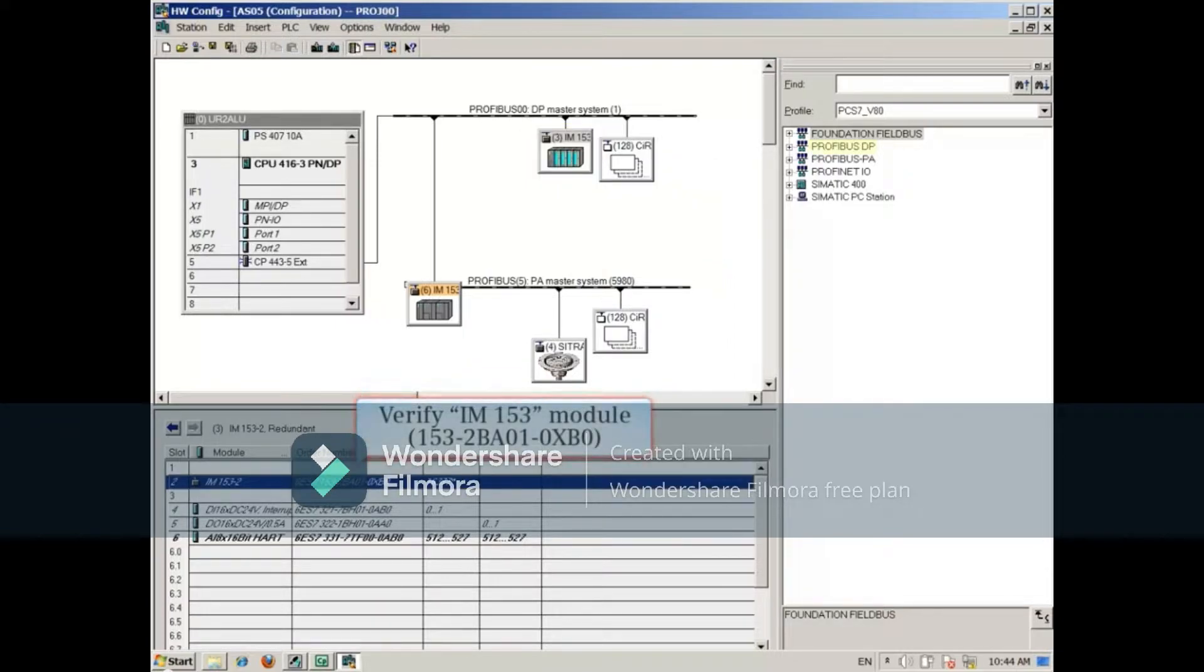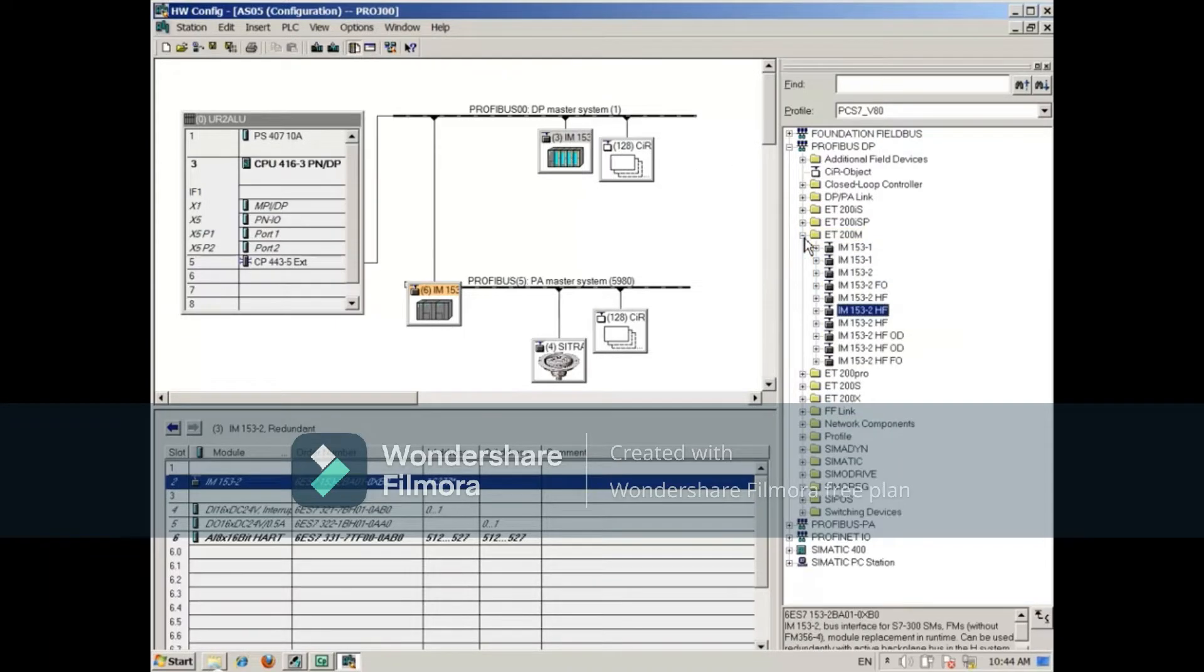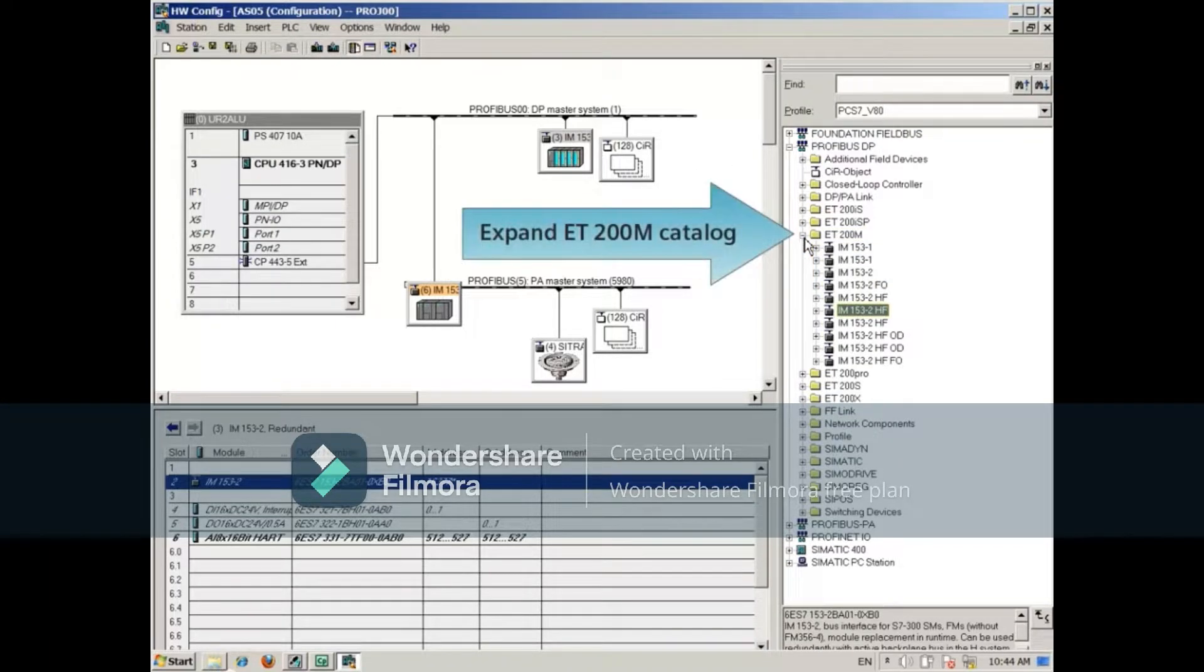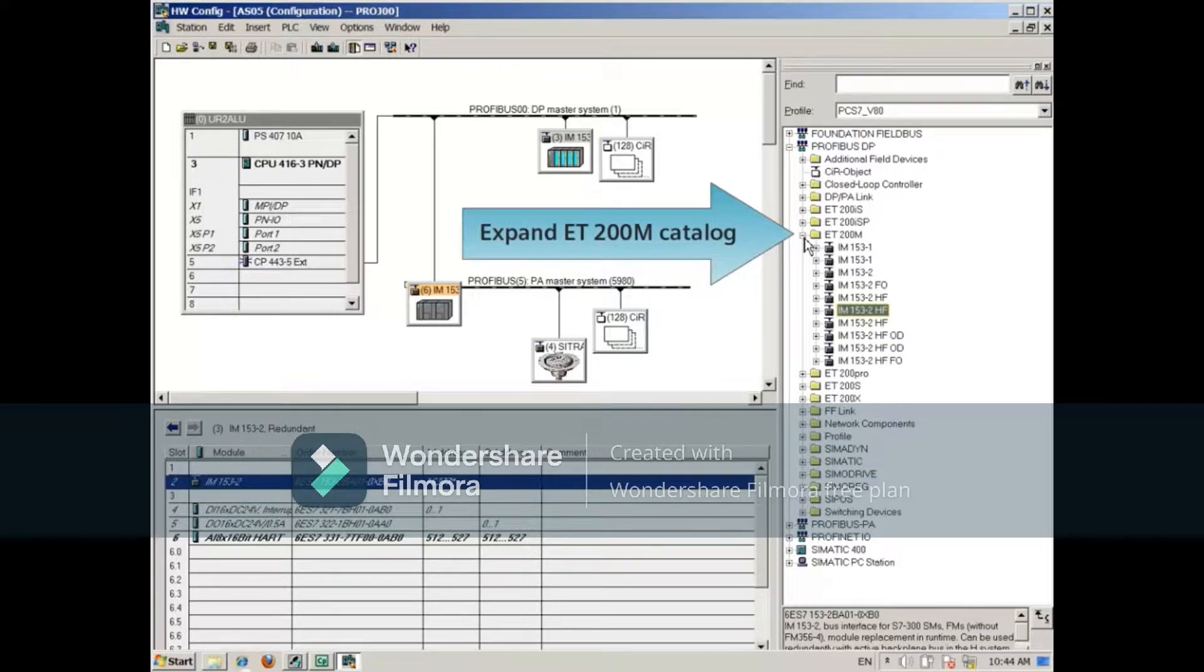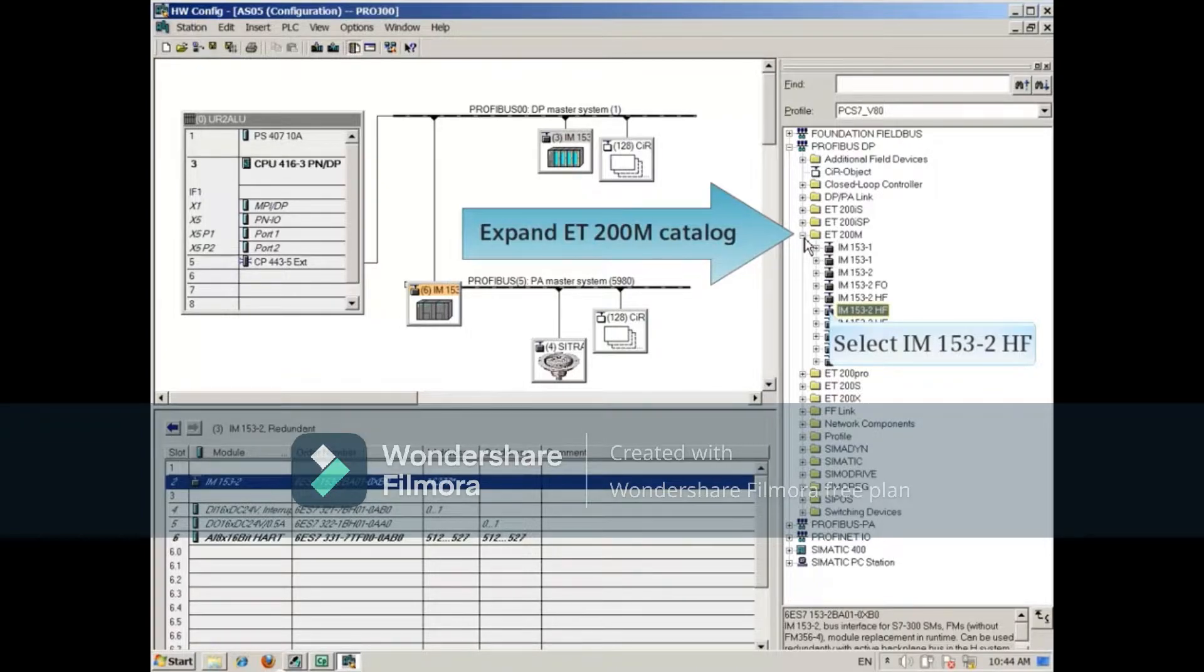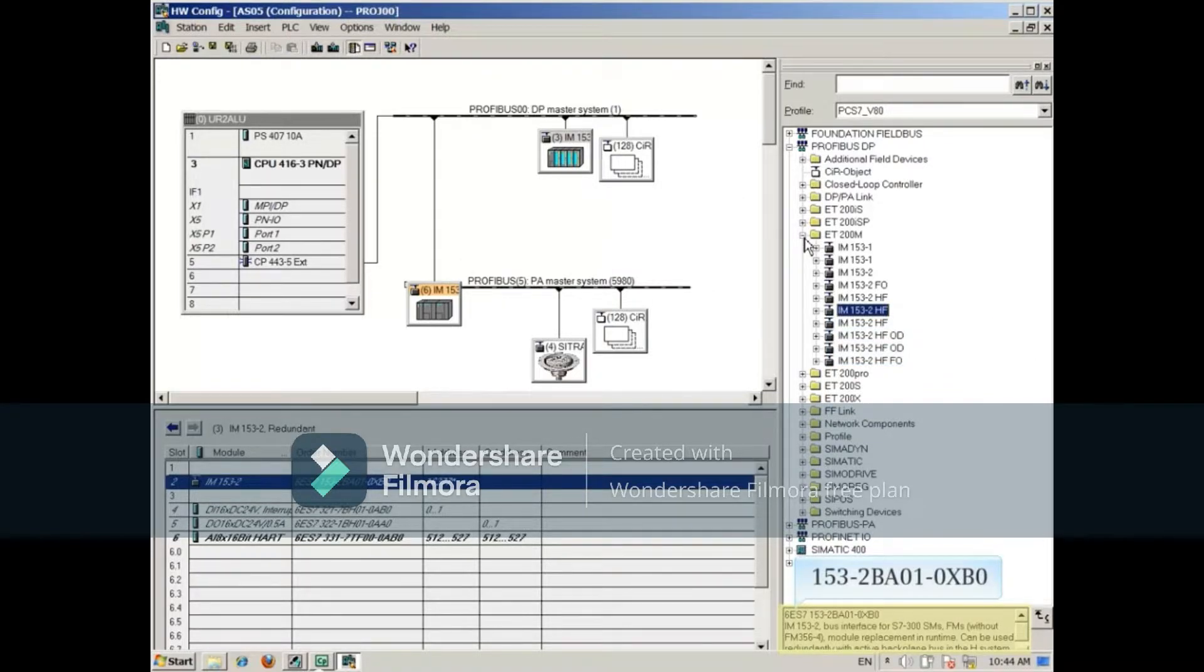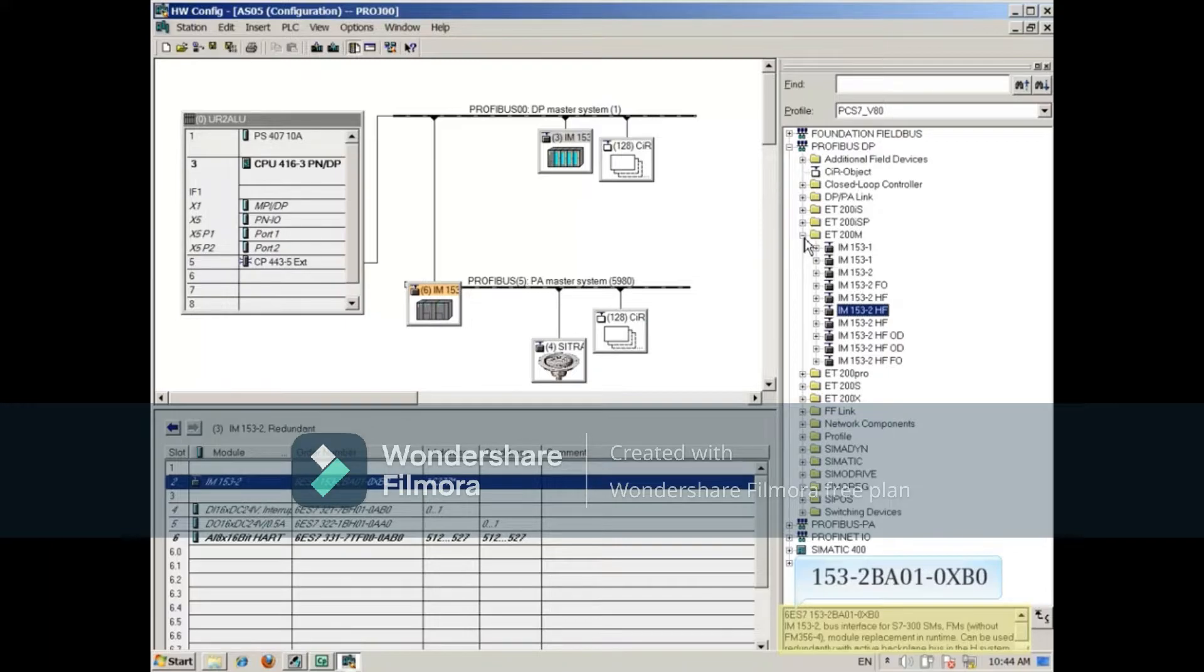Next, verify the IM153 order number in the list at the bottom. Expand the Profibus DP/ET200M catalog and select the IM153 choices until the order number at the bottom matches the one in Hardware Config. In this example, it's 153-2BA01-0XB0.